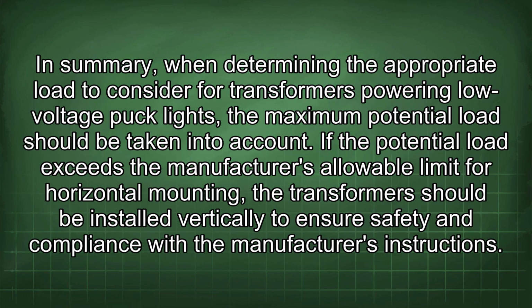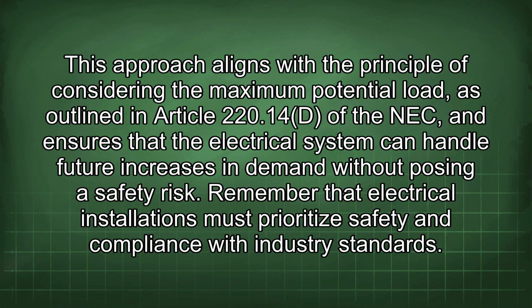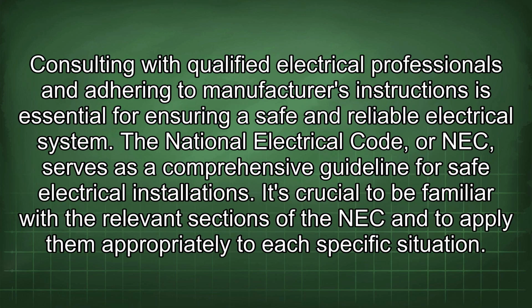In summary, when determining the appropriate load to consider for transformers powering low voltage puck lights, the maximum potential load should be taken into account. If the potential load exceeds the manufacturer's allowable limit for horizontal mounting, the transformer should be installed vertically to ensure safety and compliance with the manufacturer's instructions. This approach aligns with the principle of considering the maximum potential load, as outlined in Article 220.14(D) of the NEC, and ensures that the electrical system can handle future increases in demand without posing a safety risk. Remember that electrical installations must prioritize safety and compliance with industry standards. Consulting with qualified electrical professionals and adhering to manufacturers' instructions is essential for ensuring a safe and reliable electrical system.